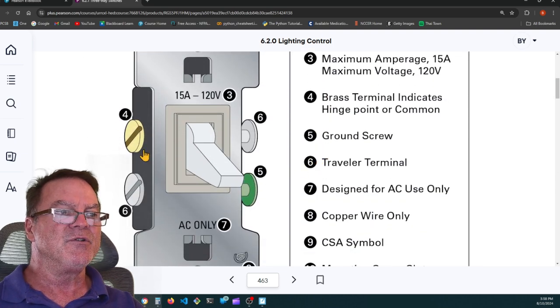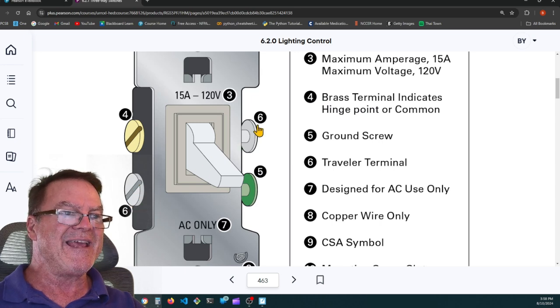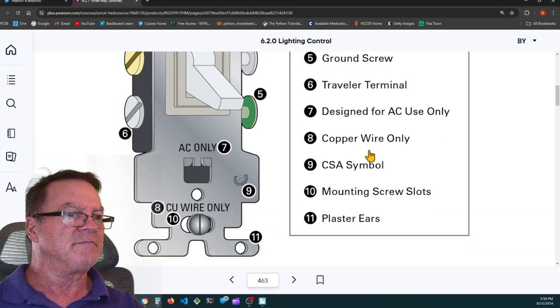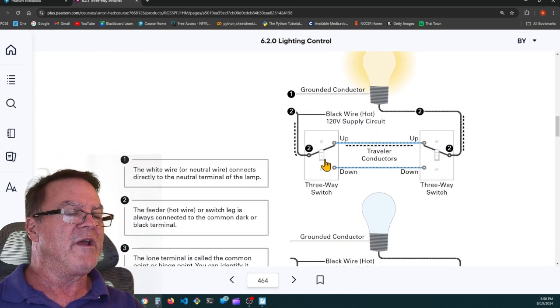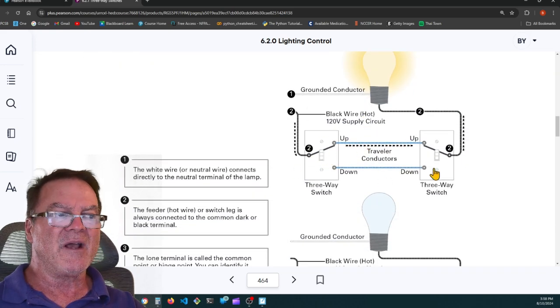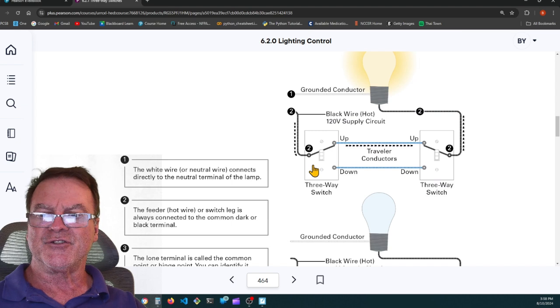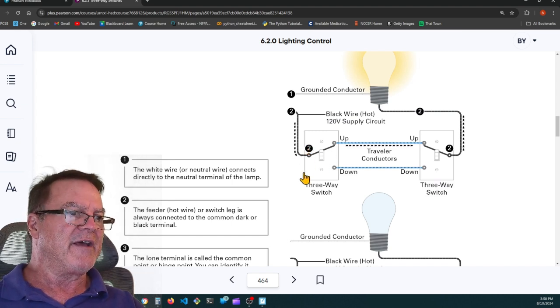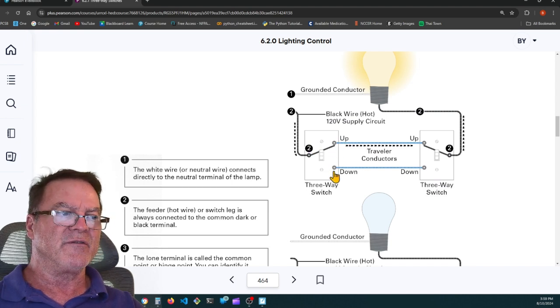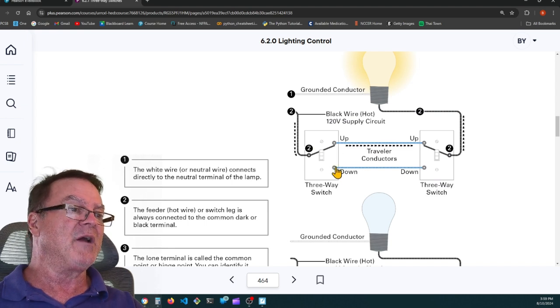It has a common screw and two travelers. The two travelers are the same color. The common screw is of a different color. So the way it works is you've got two three-way switches, and I'm not going to say these are drawn exactly as in the real world. These are just representative. So you might have two screws on one side, one screw on the other side, and I don't know that the two travelers are on the same side of the screw. Sometimes the travelers are on the top of the switch, and the common is on the bottom of the switch. But this is the way they have it drawn.